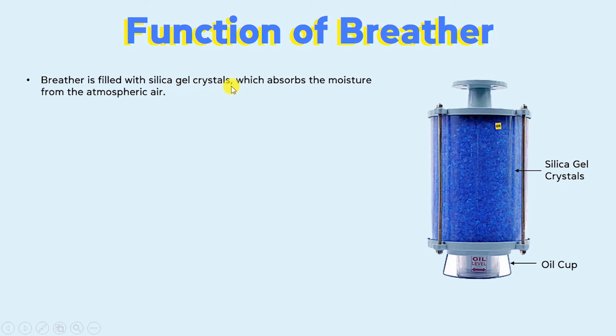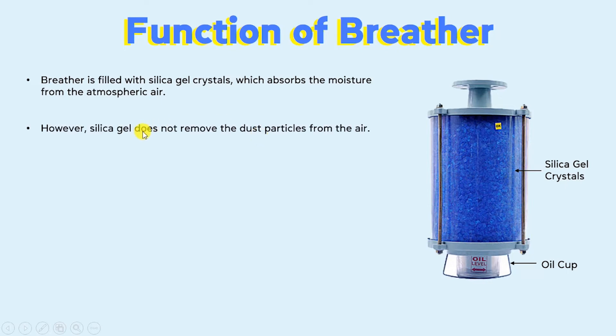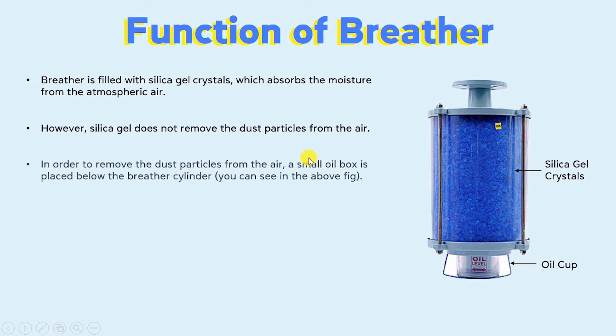Now let's discuss the function of breather. The breather is filled with silica gel crystals which absorb the moisture from the atmospheric air. As you can see in the diagram, these are the silica gel crystals which absorb moisture from the atmospheric air. However, one disadvantage of silica gel crystals is that they don't remove the dust particles from the air. In order to remove the dust particles, a small oil cup is placed below the breather cylinder.